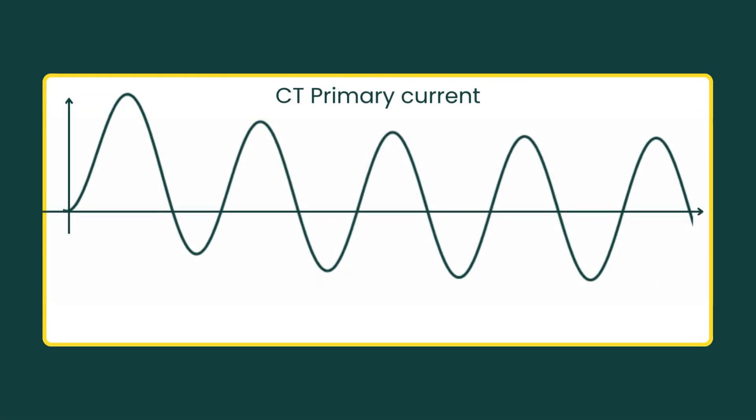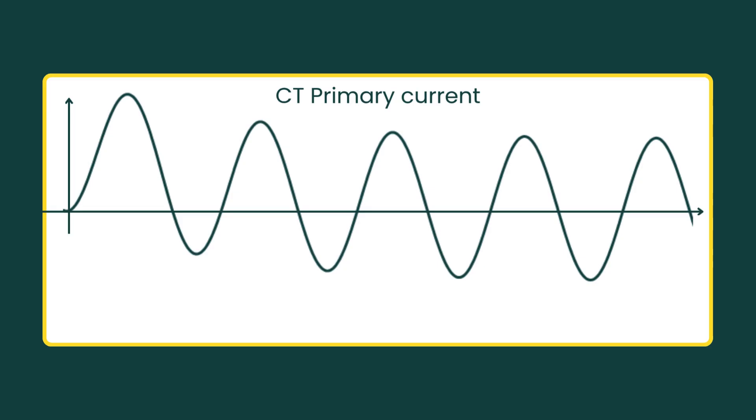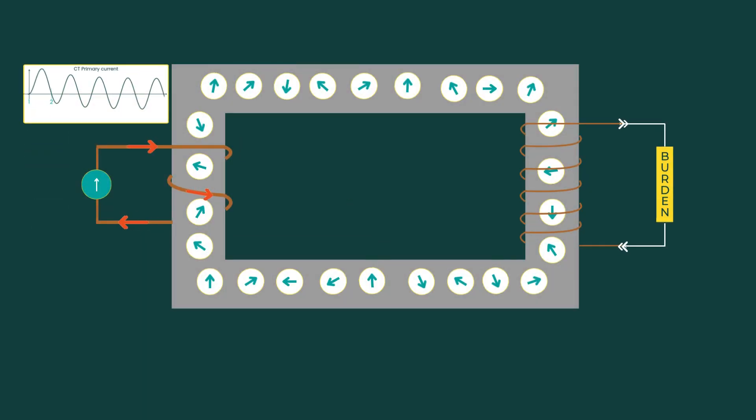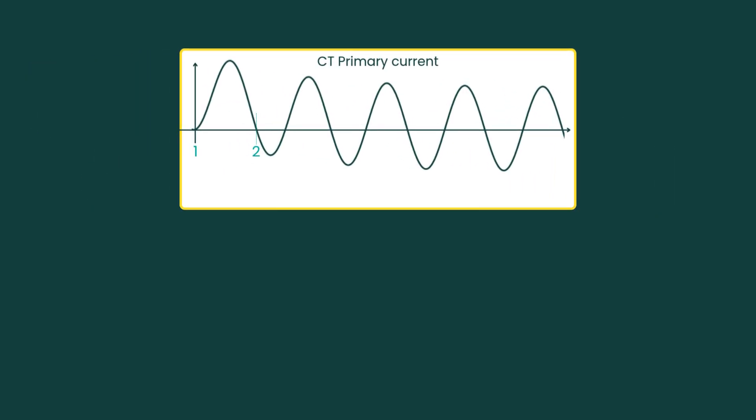Now let's walk through the first few cycles and see what happens inside the CT during those early moments. During the first positive half cycle, from point 1 to point 2, the current is positive and the dipoles in the core begin lining up in the positive direction. The flux is changing, so the CT works as expected; the secondary current follows the primary current, scaled by the CT ratio.